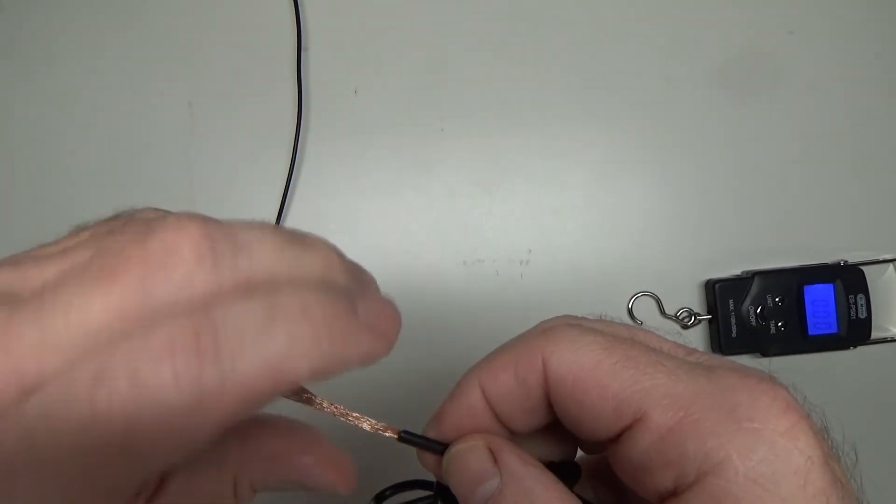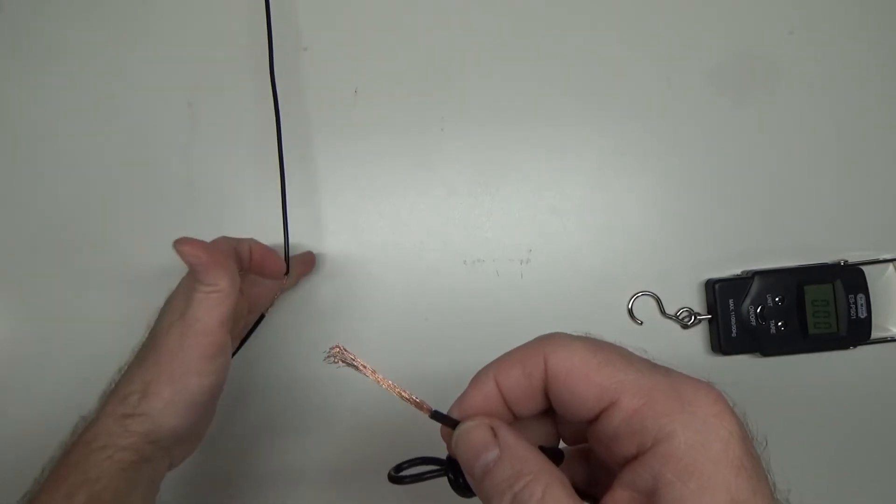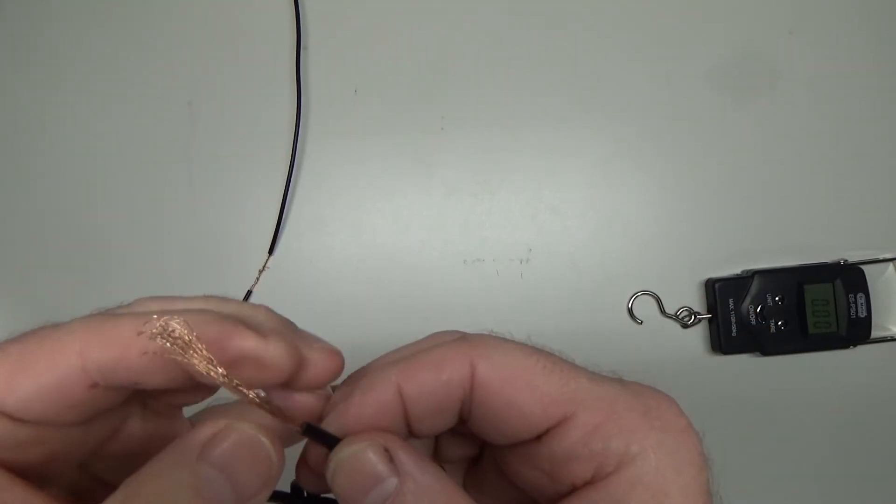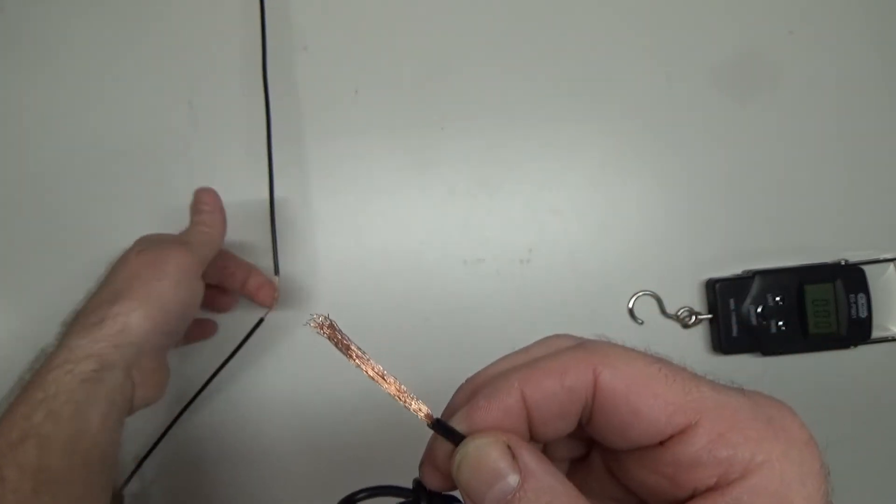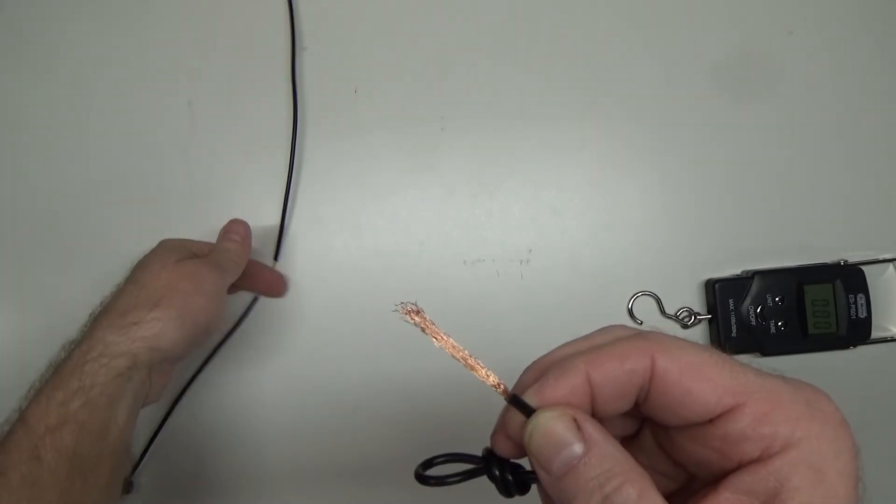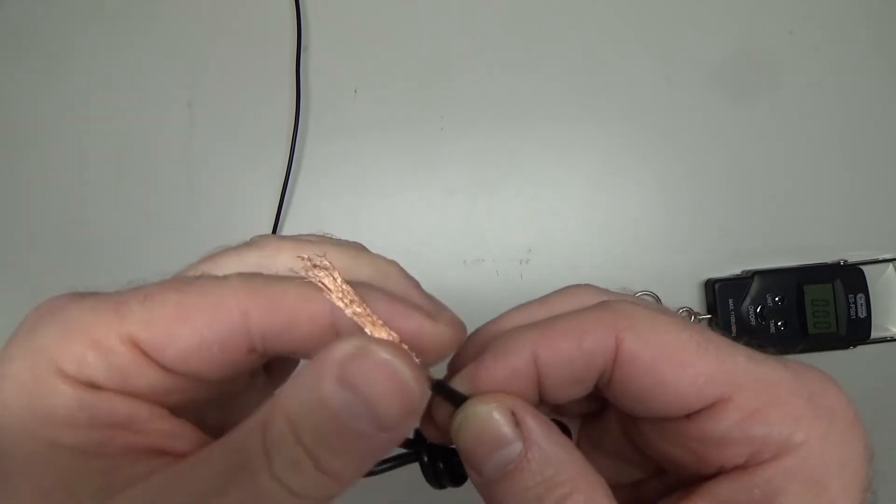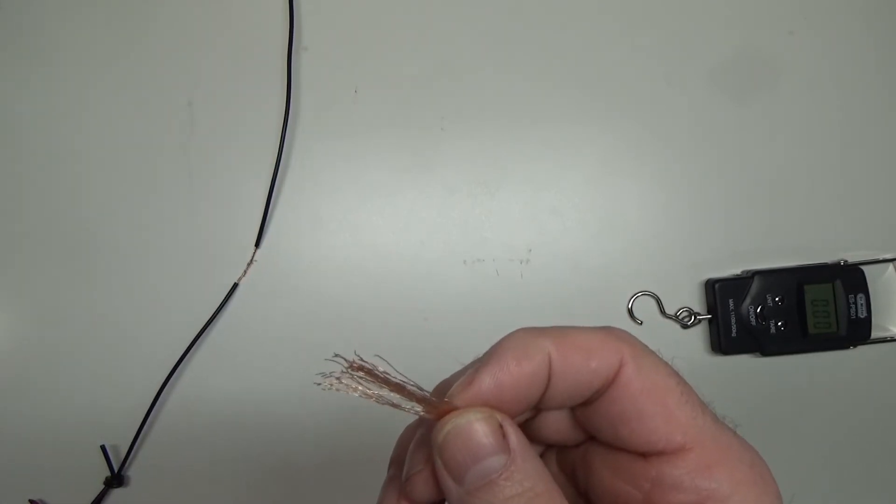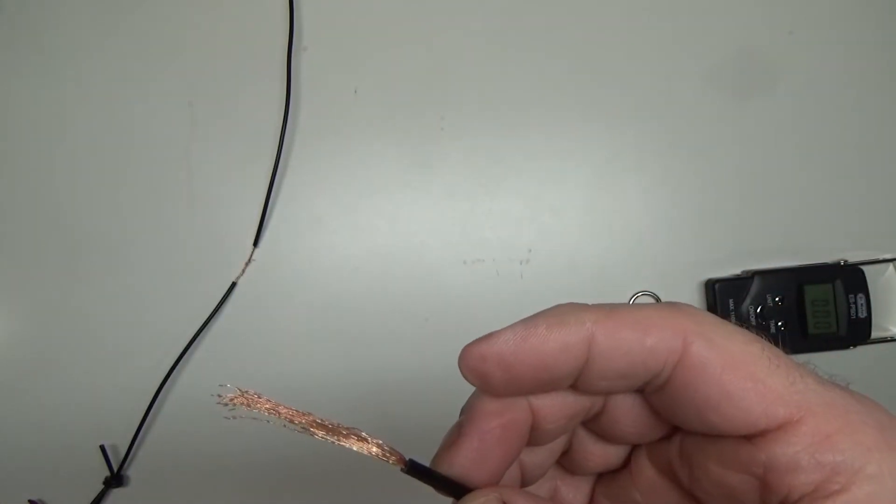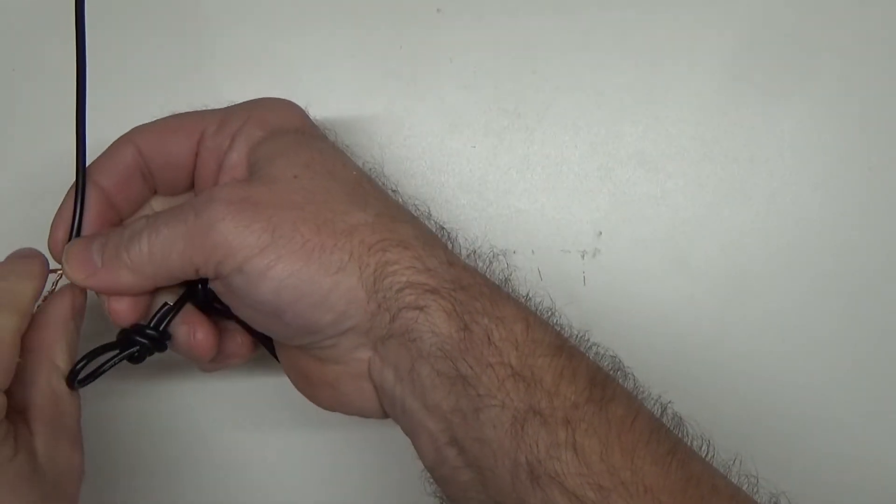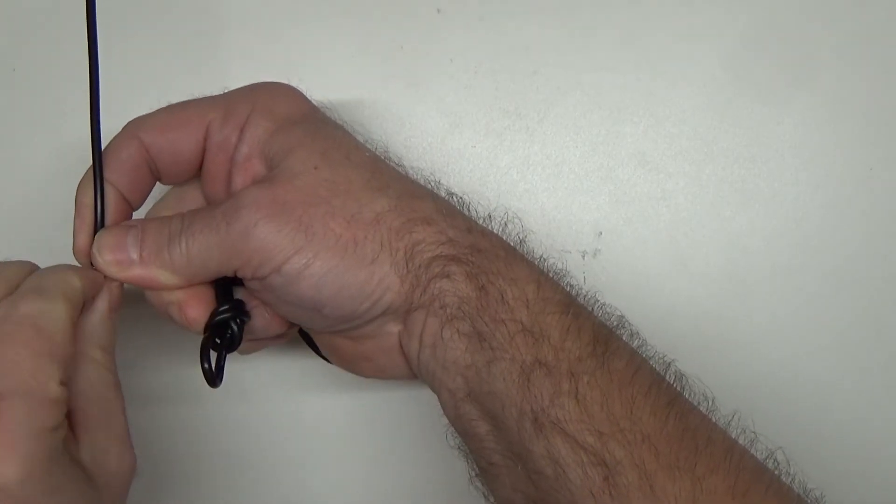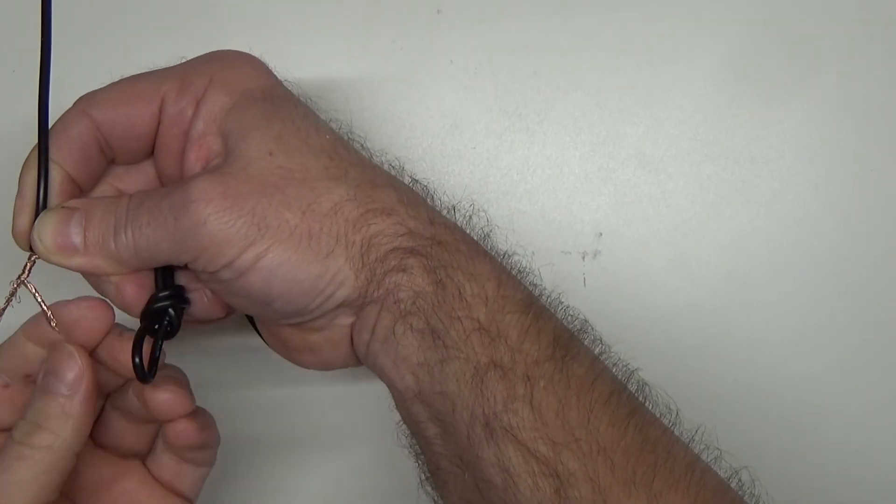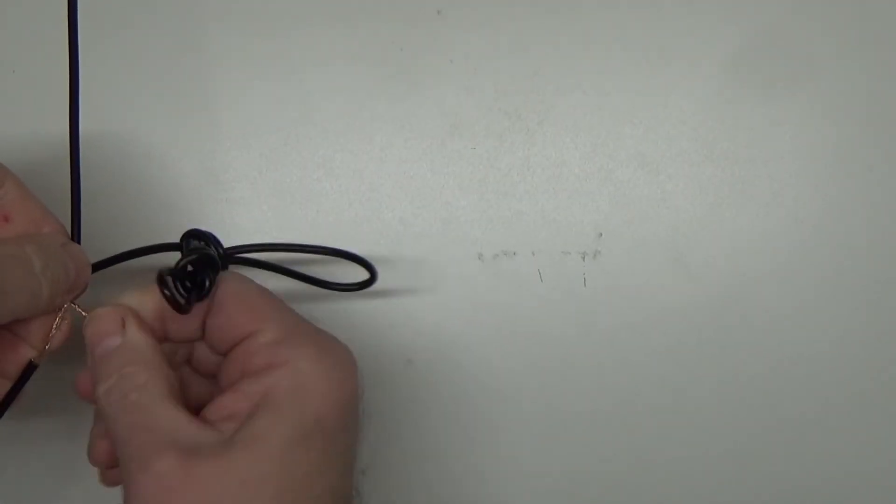If you just take and wrap this around like straight here first, just wrap like that, then wrap it around the wire, it's not as strong. I've never measured the pull, but I can tell you it's just not as strong. But taking the strands and keeping them frayed out, the wires actually wrap over this, but these also wrap over themselves, so it's a much stronger wrap by keeping them frayed out like that and wrapping around. You know what, for kicks and giggles, let's try it. I'm going to twist this then wrap around that. We got this wrap around there, let's wrap around here again, using the same method. I'm pulling the wire, keeping it tight as I wrap it. Your fingers tend to want to unwrap a little bit as you pull it.